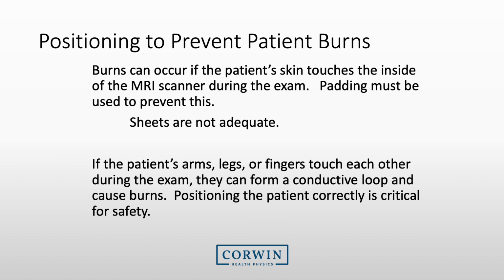There have been some recent events as well when burns occurred due to the patient's skin touching the inside of the MRI scanner. Padding should be used around the patient to prevent contact with the bore. Also, you should discourage the patient from forming loops with their arms, legs, or fingers in order to prevent conductive loops that can cause burns.